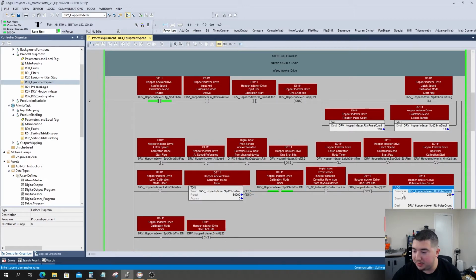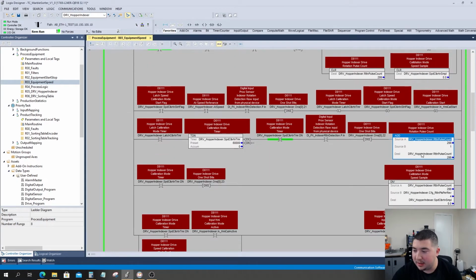With each pulse, we'll increment this counter, and this is just a constant accumulation counter. Every time we get a pulse, it'll add 1 to the current value, and then once the timer has completed, or after a full minute of pulses, we will stop counting, and this will be our final count for our rotational speed.